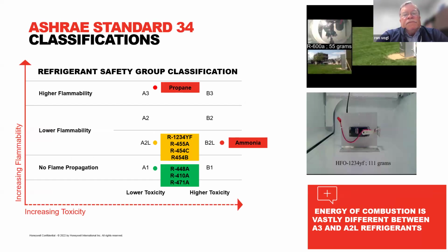Talking about flammability and how things are rated, this is just a chart on how ASHRAE breaks it down. Historically we used A1, things like 448, 410, skip the 471 description, but for the 407 series, all those were A1s, 134 could be in there too. Low to no toxicity, non-flammable.